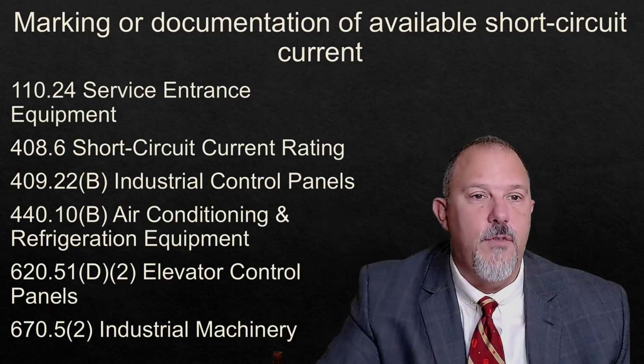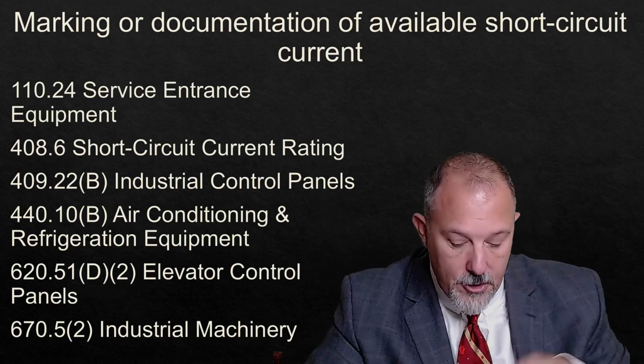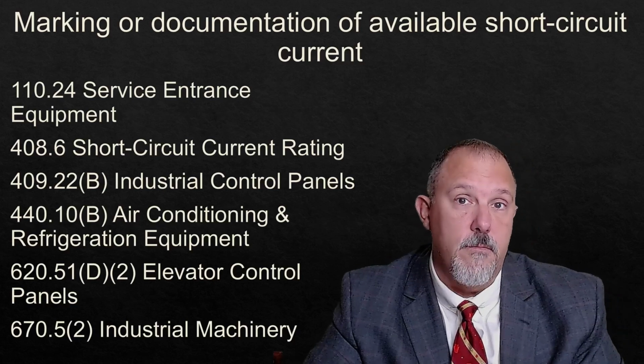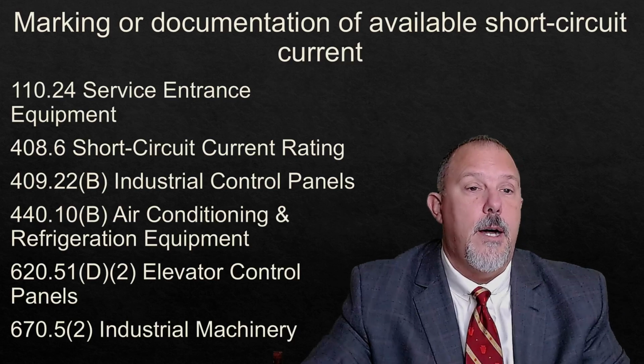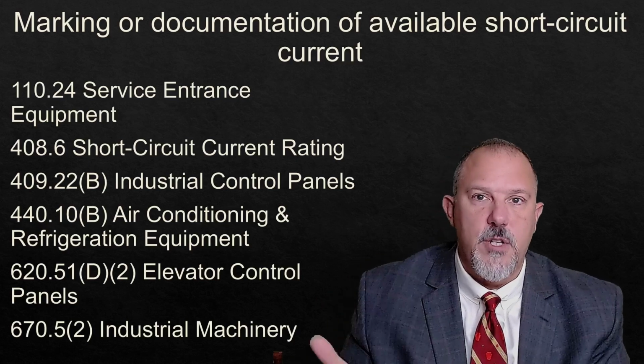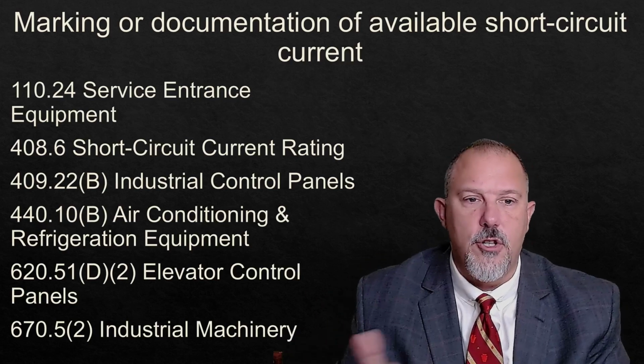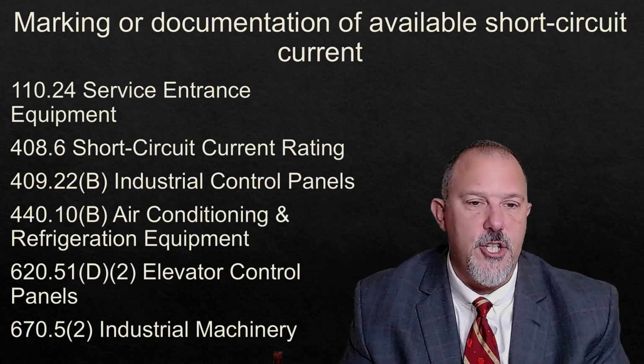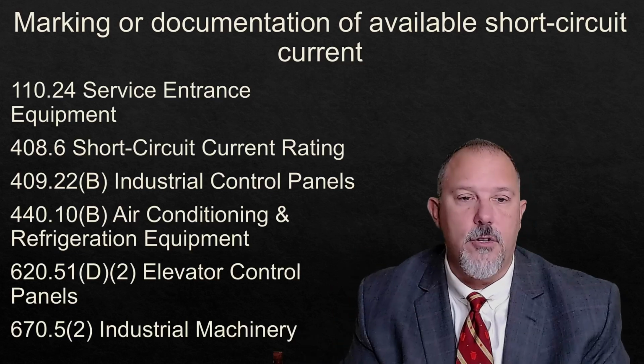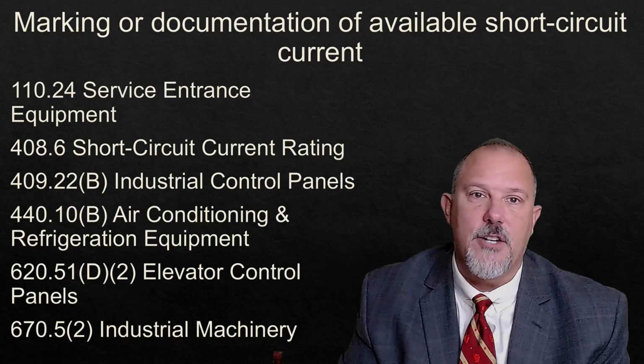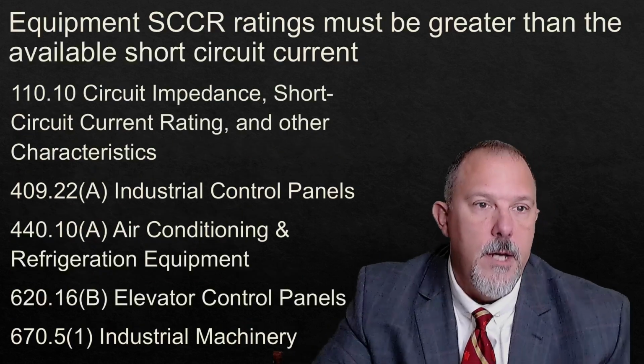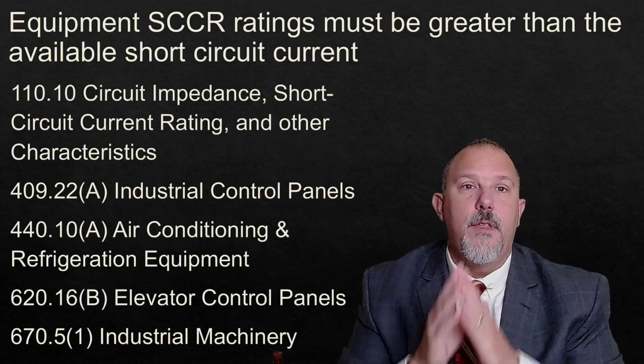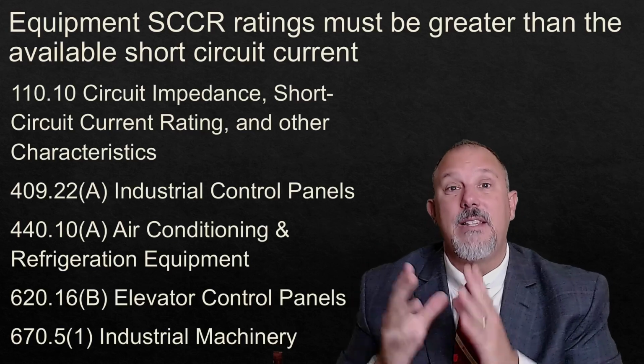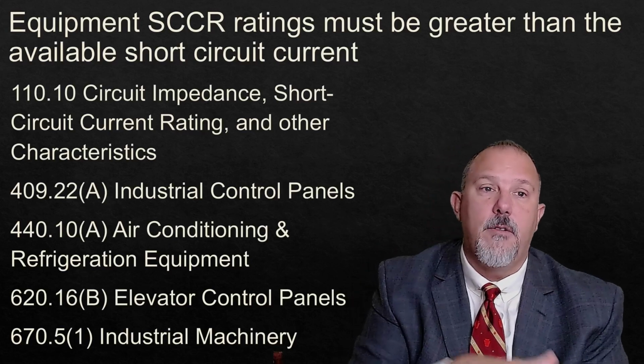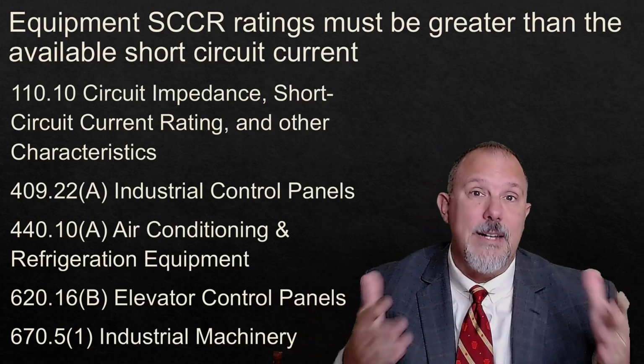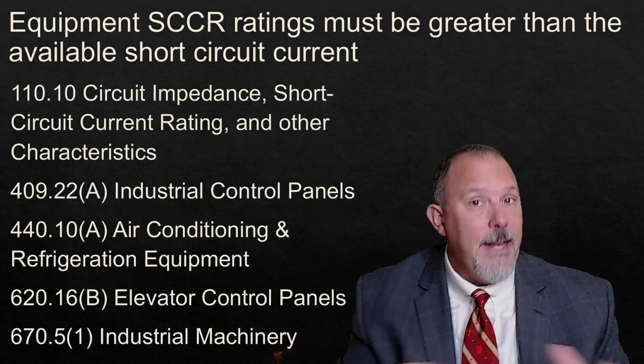So 110.24 tells us about service entrance equipment. 408.6, panel boards, switchboards, and switchgear. 409, industrial control panels. 440, air conditioning and refrigeration. 620, elevator control panels. 670, industrial machinery. Now, these are the sections of the code that tell you the SCCR rating must be greater than the available short circuit current. 110.10 is our reference for that for any application.